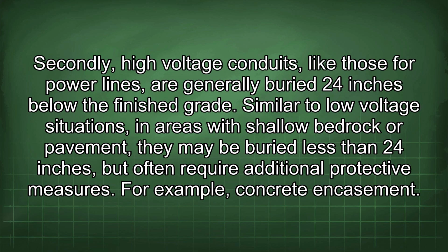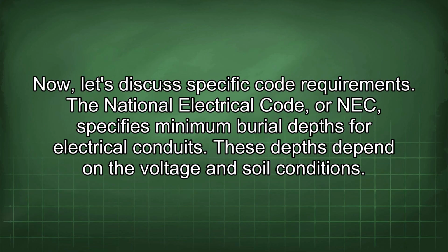Secondly, high-voltage conduits, like those for power lines, are generally buried 24 inches below the finished grade. Similar to low-voltage situations, in areas with shallow bedrock or pavement, they may be buried less than 24 inches but often require additional protective measures. For example, concrete encasement. Now let's discuss specific code requirements.